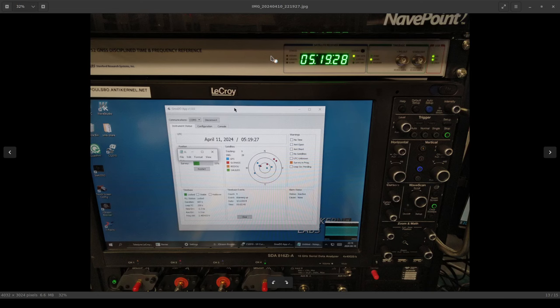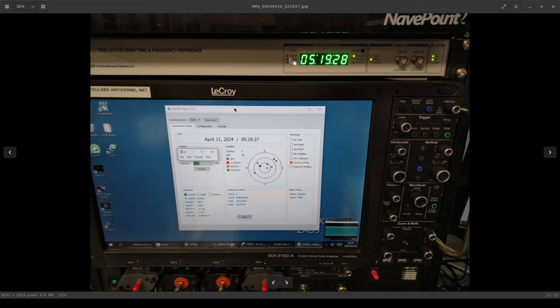Looking at the front panel of the instrument we can see there's a couple of different LED indicators. There's an antenna problem alert, there's a general out of tolerance alert. This one here will turn green when it's completed the survey. This picture was taken right after I had hooked up the unit and so it's still figuring out where it is and getting the loop in lock.